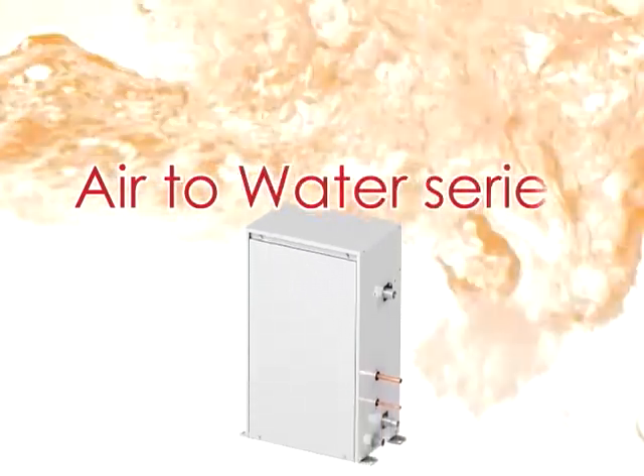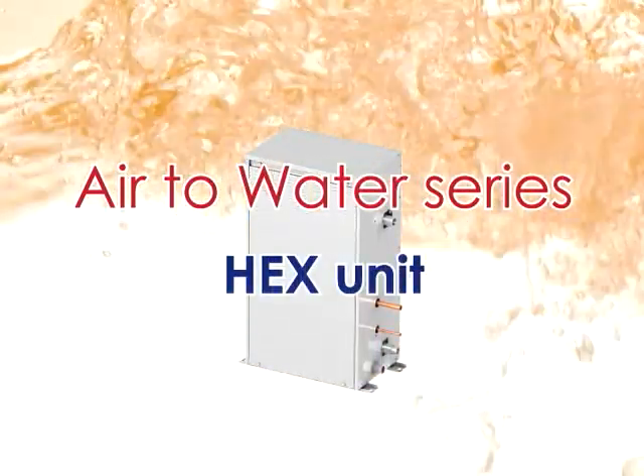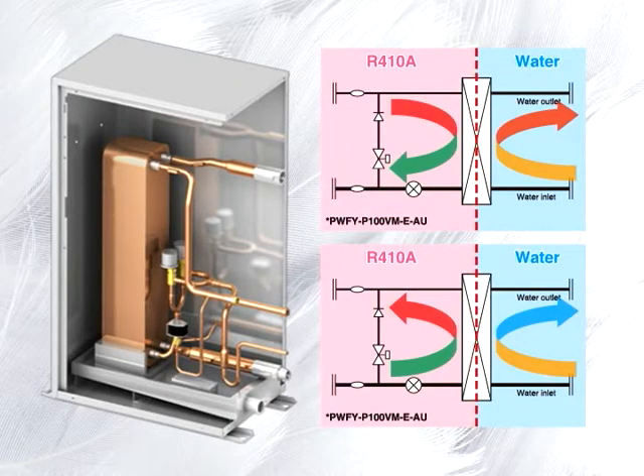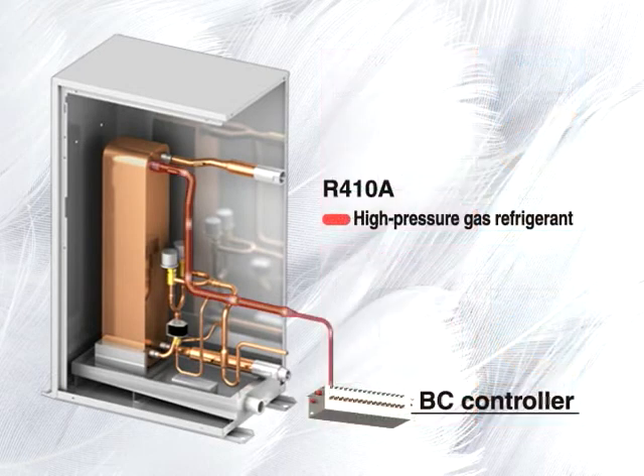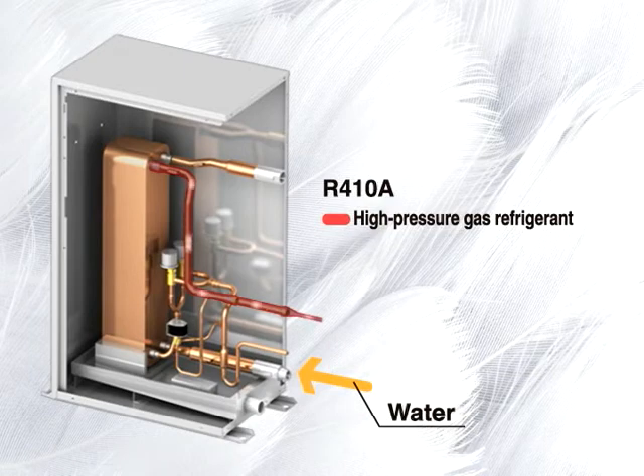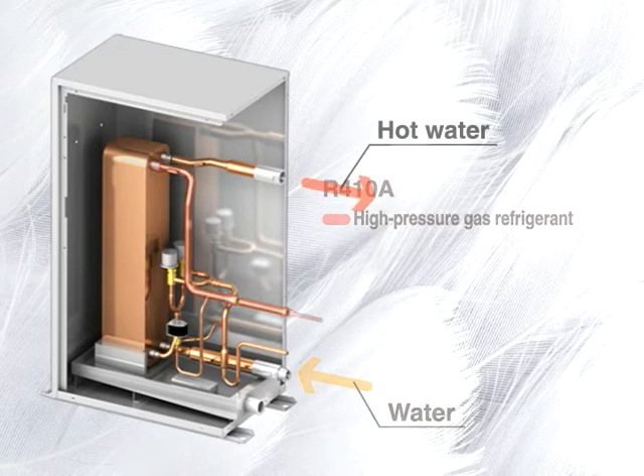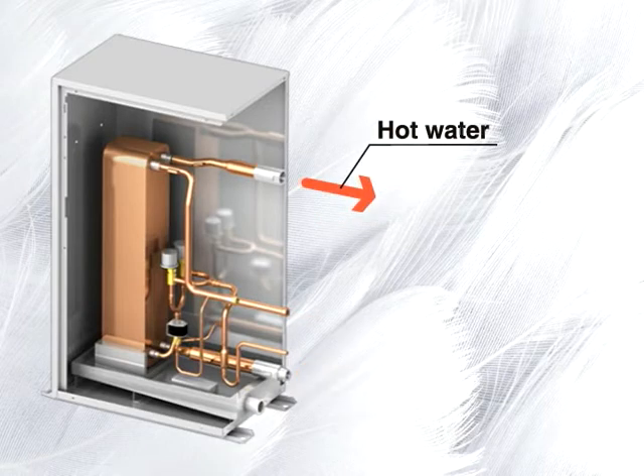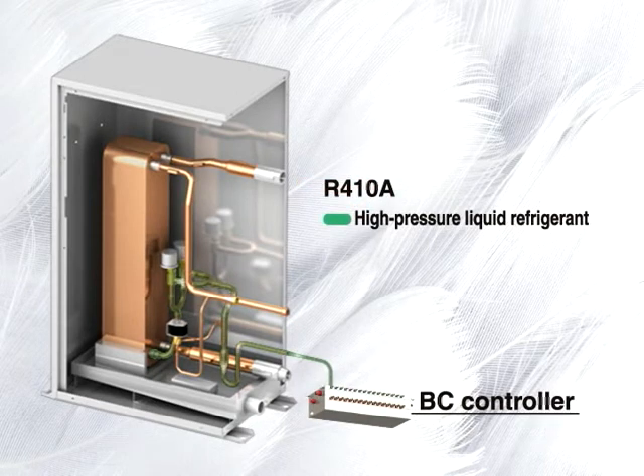Next, let's take a closer look at the air-to-water heat exchanger unit. Heat exchanger units are not equipped with compressors. In an R2 system, high-pressure R410A gas refrigerant is delivered from the BC controller. Water entering the heat exchanger unit is heat exchanged with the high-pressure R410A gas refrigerant to supply hot water. Gas refrigerant carrying away heat returns to the BC controller as a high-pressure liquid refrigerant. Hot water up to 45 degrees Celsius can be provided with heat exchanger units. Moreover, they not only can supply hot water, they can also supply cold water down to 10 degrees Celsius.